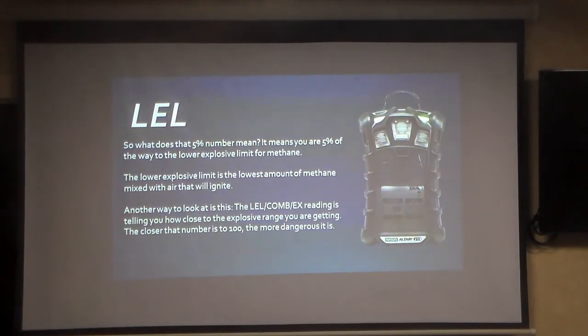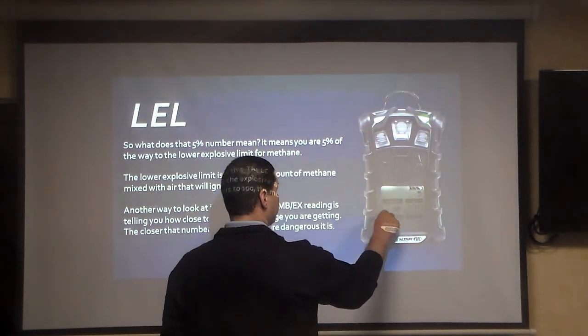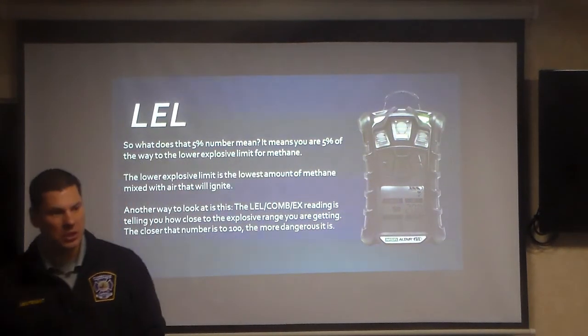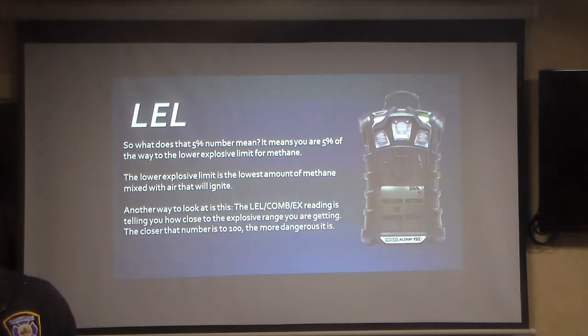All right. Just a little refresher on the LEL and what the LEL means, right? This particular sensor here, the LEL sensor, measures how close to the lower explosive limit you are getting for the gas that the meter is calibrated to. Okay? Do we understand that concept? So the meter's calibrated to, for LEL, pentane? I'm trying to remember. Either way, it's basically telling you how close to the lower explosive limit you are, right?